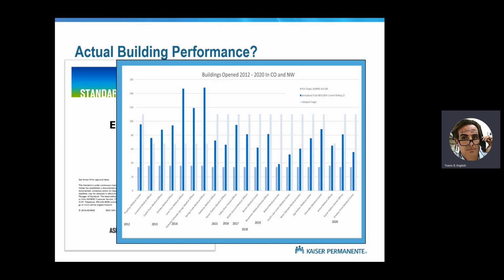Then the building opens, and its year one energy is 100 EUI. Now you need a 45% reduction by year 2 in order to meet that target. The first thing the owner is going to do is an audit. And the audit will show that they need to invest $1 million in the HVAC system in order to reach the target. To me, that's an open and shut case of design liability. And I think that owner should think about suing the design engineer to pay for what it takes to meet the code.